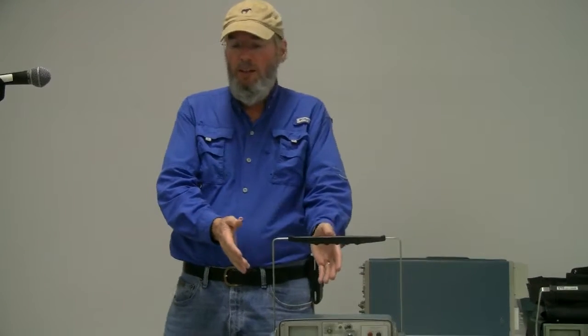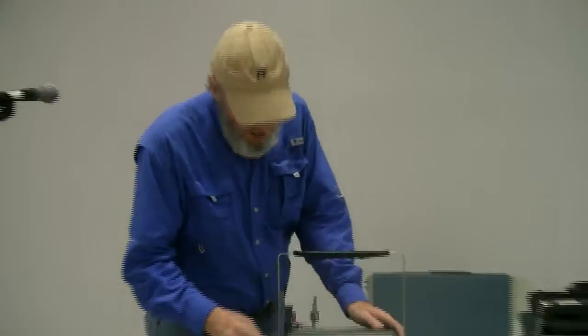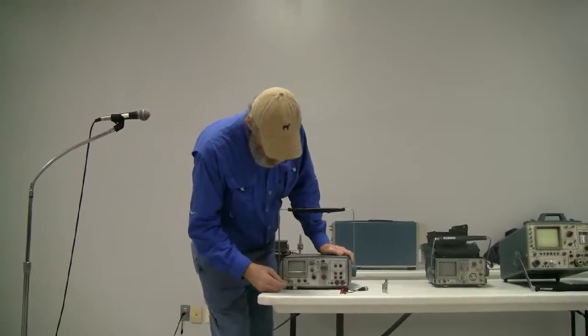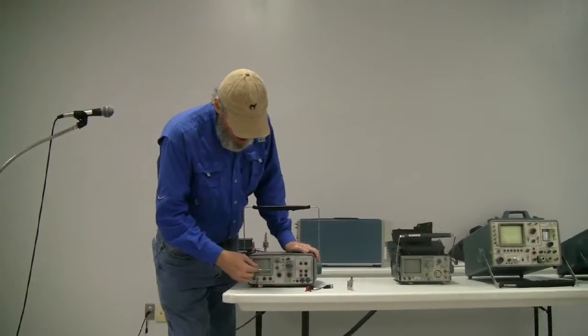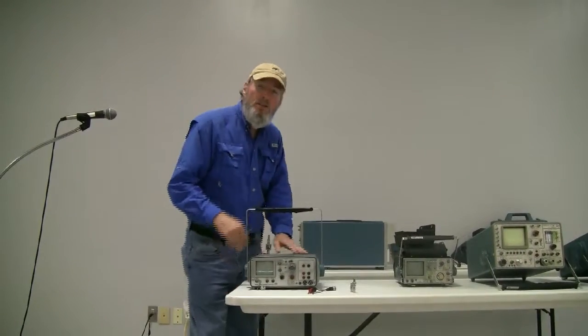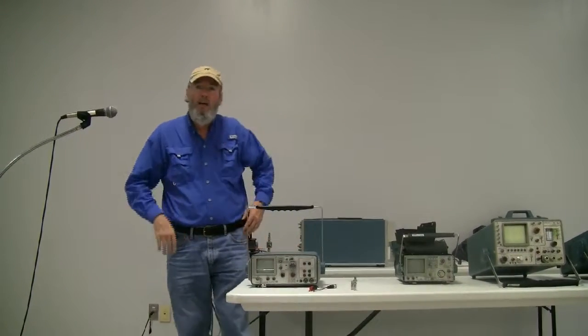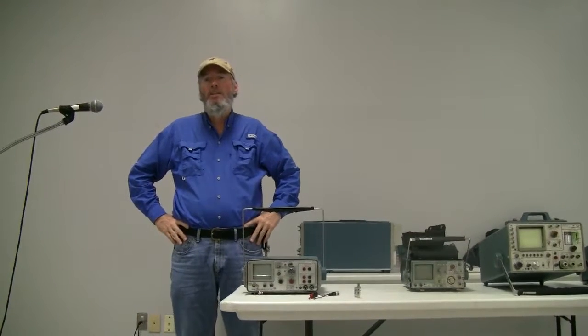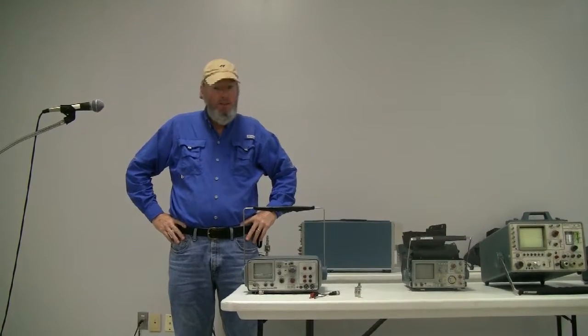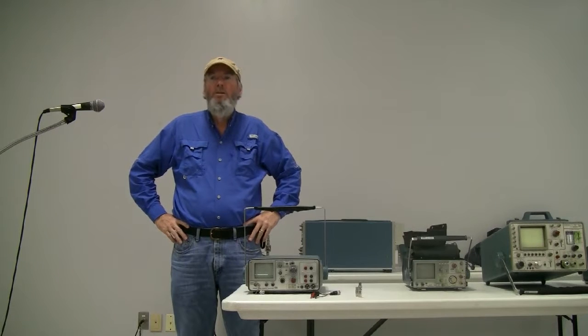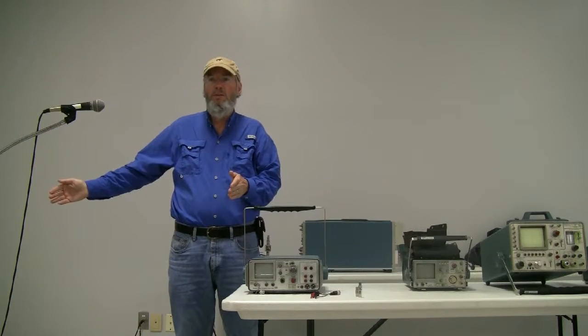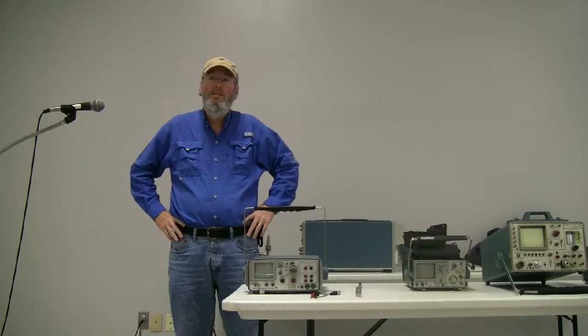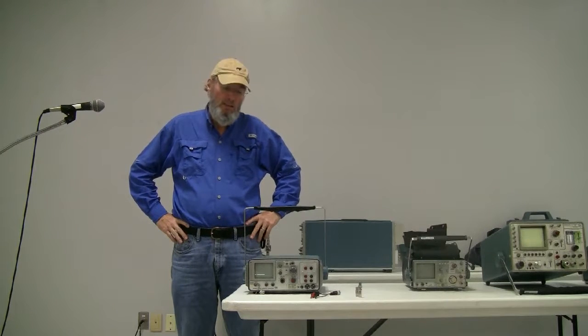On a time domain reflectometer, there are characteristic signatures. If you've got water in a piece of cable, instead of seeing a flat line where the impedance is constant, you're going to see that impedance drop, and it'll usually slope in a jagged, irregular manner as it increases. When you see that, you're thinking, okay, something's happened over a long distance in my transmission line, and water ingress is the normal cause.